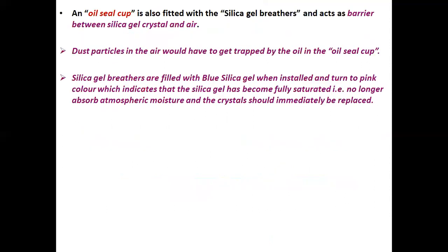An oil seal cup is also fitted with the silica gel breathers and acts as a barrier between the silica gel crystals and air. Dust particles in the air get trapped by the oil in the oil seal cup. Silica gel breathers are filled with blue silica gel when installed and turn pink, which indicates that the silica gel has become fully saturated, that is, it can no longer absorb atmospheric moisture, and the crystals should immediately be replaced.